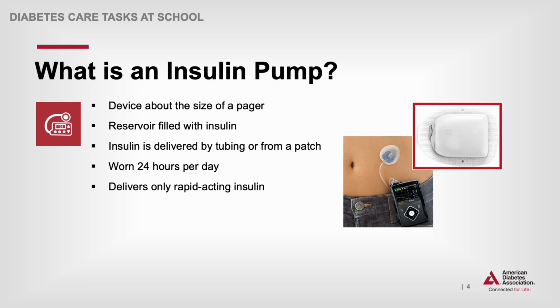Users set the pump to give a steady trickle or basal amount of insulin continuously throughout the day. Pumps release bolus doses of insulin at meals and at times when blood glucose is too high based on the user's programming. Some pumps, like the one listed on the slide, are attached directly to the body. This newer kind of insulin infusion pump is often referred to as a patch pump or pod. This type differs in that it adheres directly to the skin without using additional tubing. It is a disposable unit that is controlled by a separate PDM device. In the pod type pumps, insulin is still continuously delivered through a small plastic catheter on the underside of the pod and inserted just under the skin in the abdomen, buttocks, or thigh.